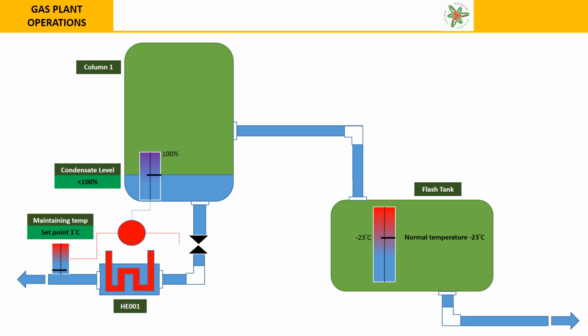So here is our process. We have column one, which has a normal condensate level shown here. The condensate flows out through the valve, through the heat exchanger, and off to a different gas plant. The exit set point from HE001 is 1 degree C. So if the temperature in column one is too low, and the product exiting HE001 is less than 1 degree C, the outlet of column 1 is closed to reduce the flow into the heat exchanger.